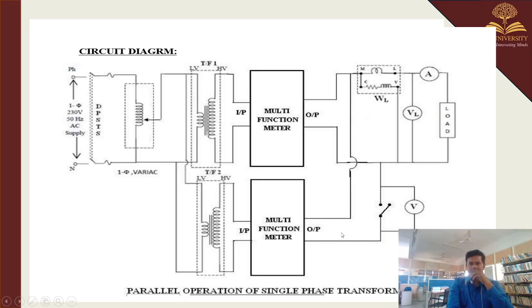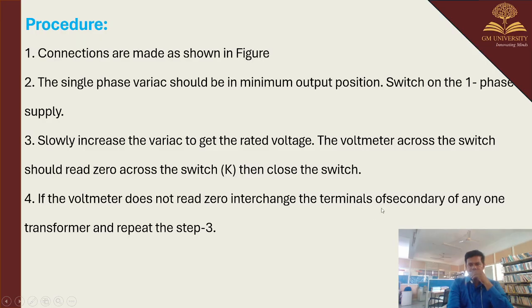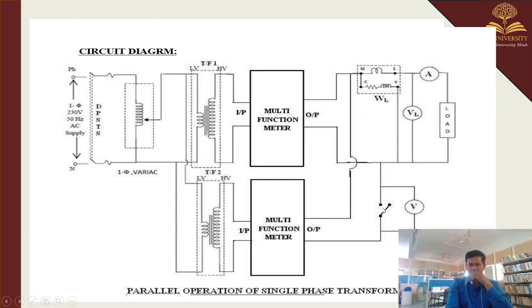And here, on the secondary of the transformers, that is, the output of the multifunction meter, we are connecting a switch. Across this switch we are connecting a multimeter to check the voltage. If the voltage reads 0, then you can close this switch. If it reads double the voltage, then you have to change one of the secondary terminals, that is, S1 and S2 should be interchanged on any one of the transformers. Then apply the loads and take the readings.